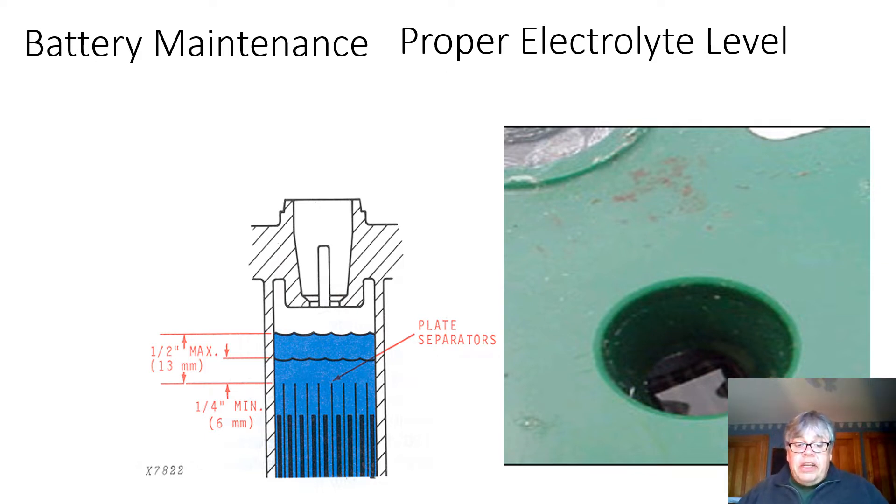If it's not, then you can add distilled water, not just tap water, not bottled water. It needs to be distilled water so there are no impurities. Otherwise that can cause a battery to fail at a much quicker pace. Can't do this if it's a maintenance-free battery.